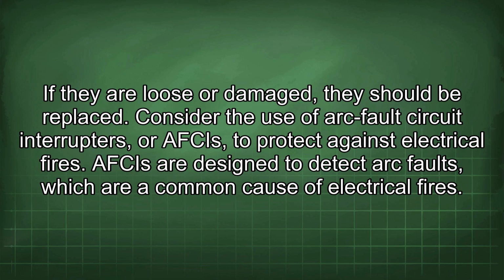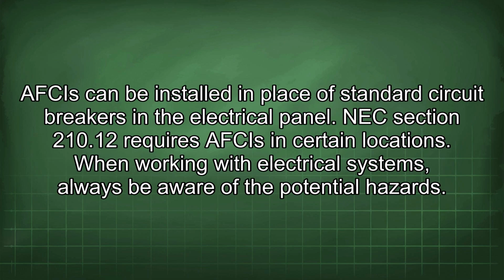Consider the use of arc fault circuit interrupters, or AFCIs, to protect against electrical fires. AFCIs are designed to detect arc faults, which are a common cause of electrical fires. AFCIs can be installed in place of standard circuit breakers in the electrical panel. NEC Section 210.12 requires AFCIs in certain locations.